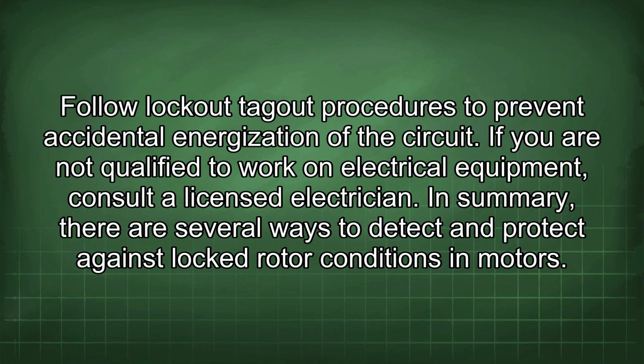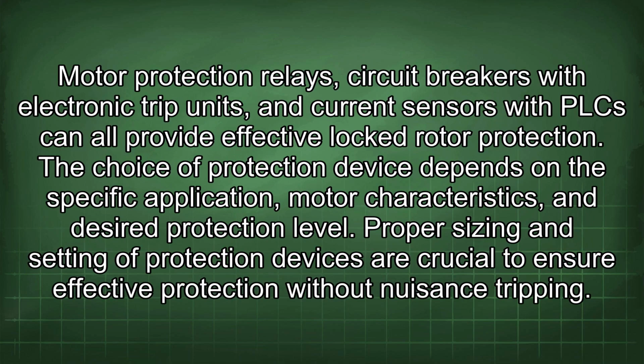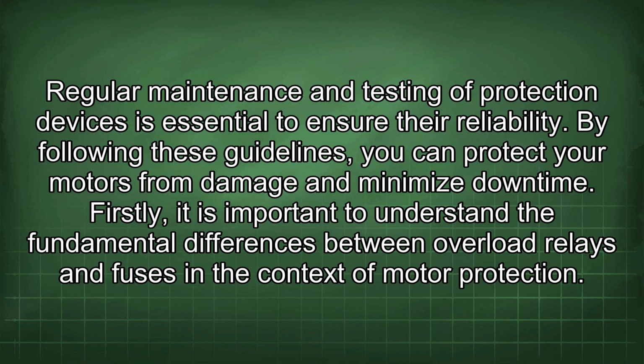In summary, there are several ways to detect and protect against locked rotor conditions in motors. Motor protection relays, circuit breakers with electronic trip units, and current sensors with PLC can all provide effective locked rotor protection. The choice of protection device depends on the specific application, motor characteristics, and desired protection level. Proper sizing and setting of protection devices are crucial to ensure effective protection without nuisance tripping. Regular maintenance and testing of protection devices is essential to ensure their reliability. By following these guidelines, you can protect your motors from damage and minimize downtime.